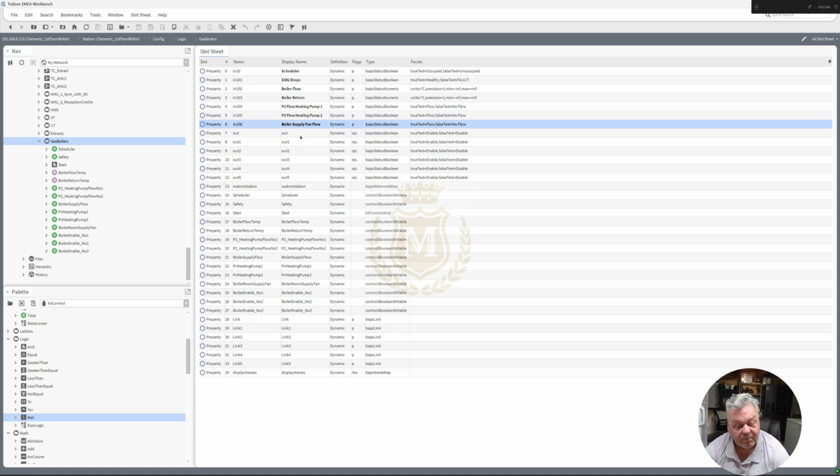I mean, what does a DP cost across the fans? I know we're going to have to wire them in, but you're looking at £6, £7, or a tenner, and then you've got to wire it in back to the panel, and hopefully we've got our spare input. But it's quite important that.